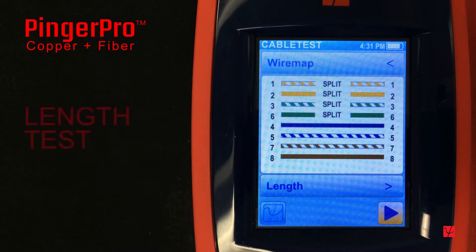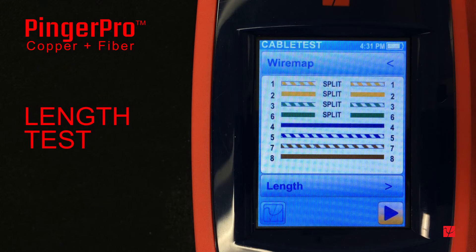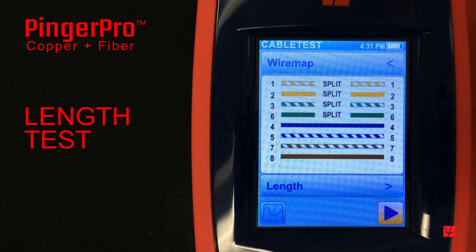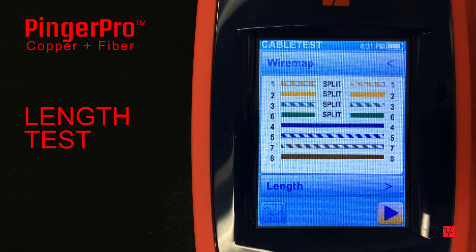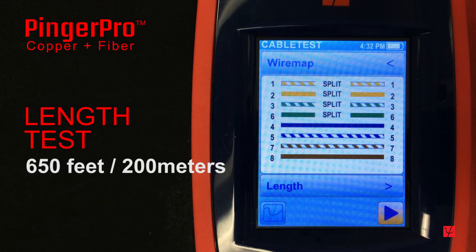A length test is used to electrically measure the length of a cable or identify an open or short fault and give the distance to the fault. This test is run from just one end of the cable and can be run from either end. The Pinger Pro will measure cable lengths up to 650 feet or about 200 meters.